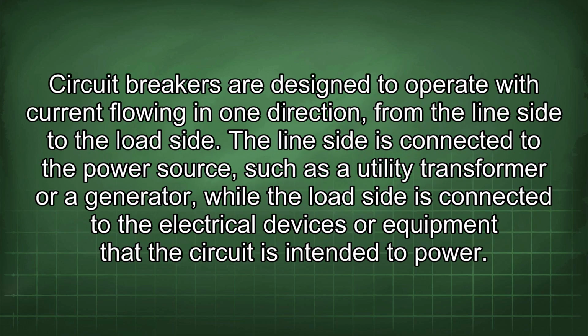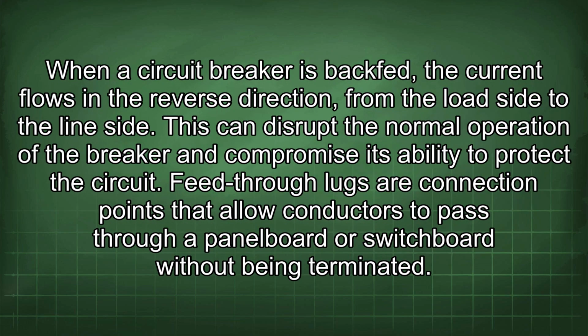Circuit breakers are designed to operate with current flowing in one direction, from the line side to the load side. The line side is connected to the power source, such as a utility transformer or generator, while the load side is connected to the electrical devices or equipment that the circuit is intended to power. When a circuit breaker is backfed, the current flows in the reverse direction from the load side to the line side. This can disrupt the normal operation of the breaker and compromise its ability to protect the circuit.